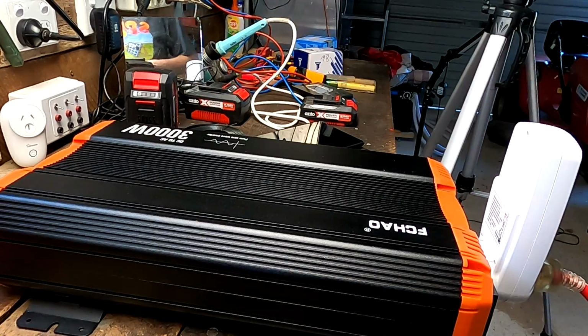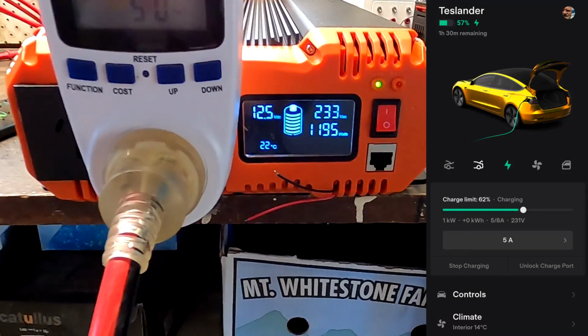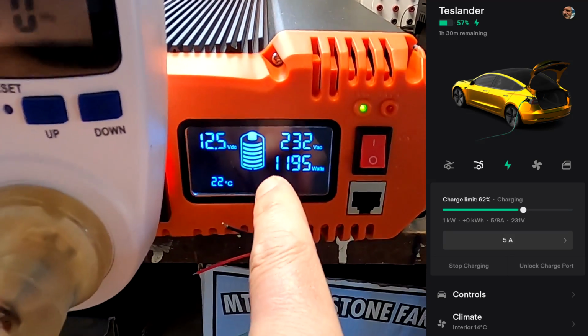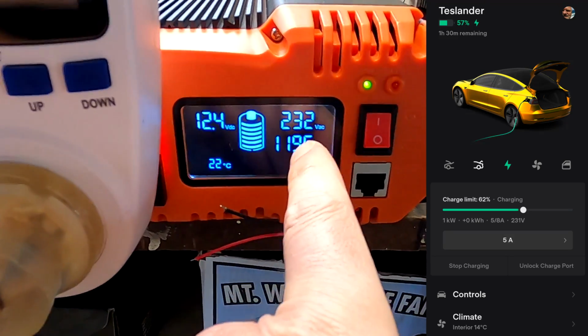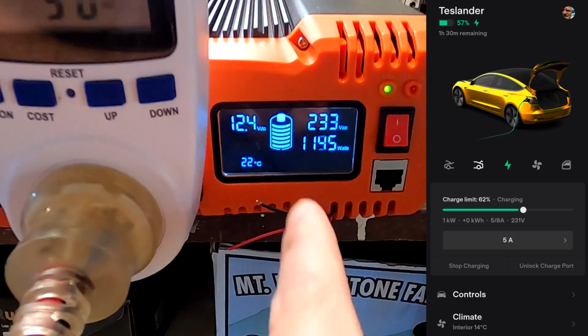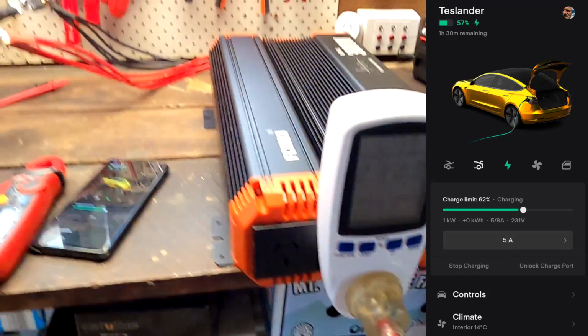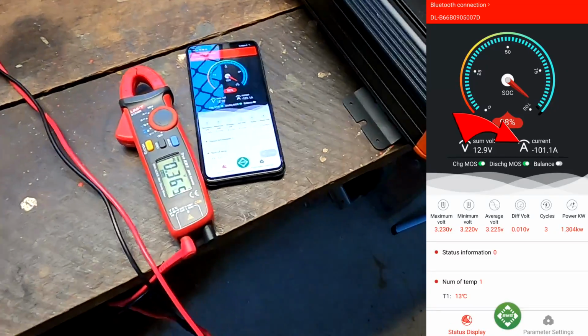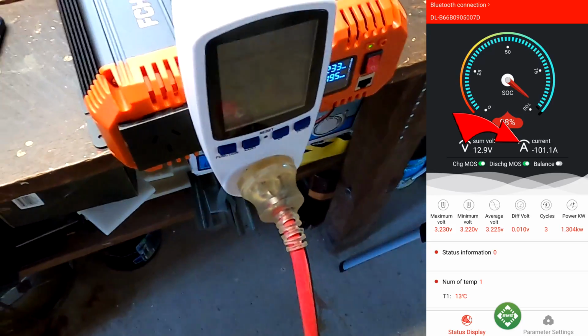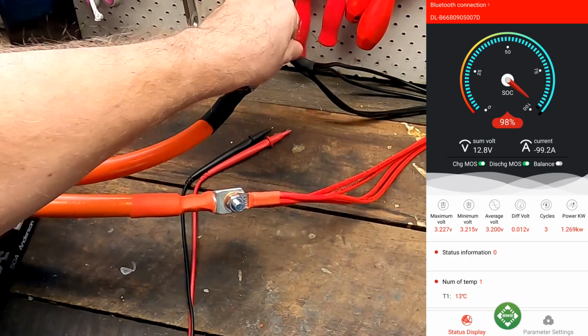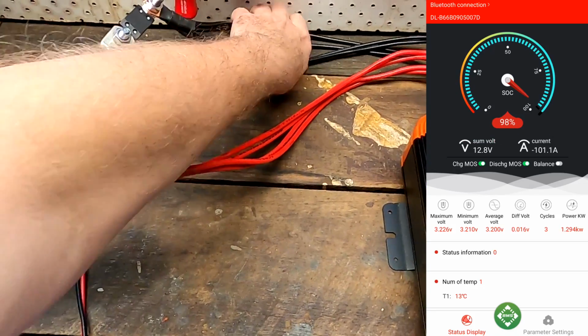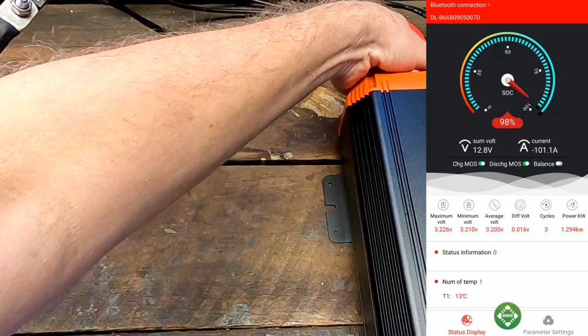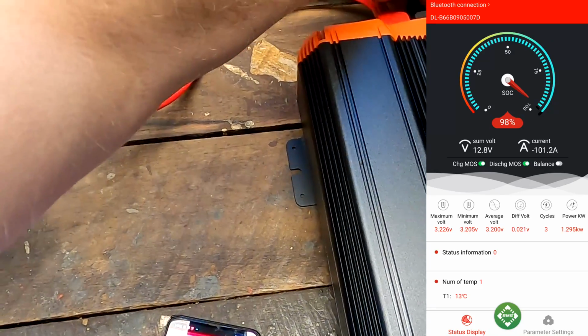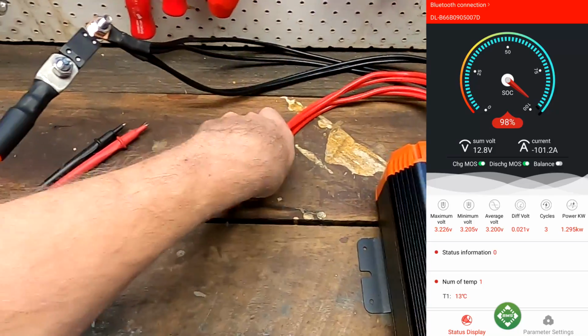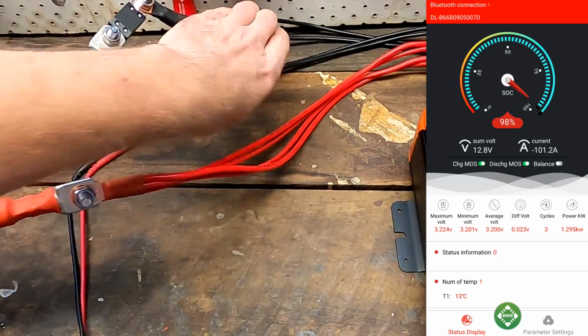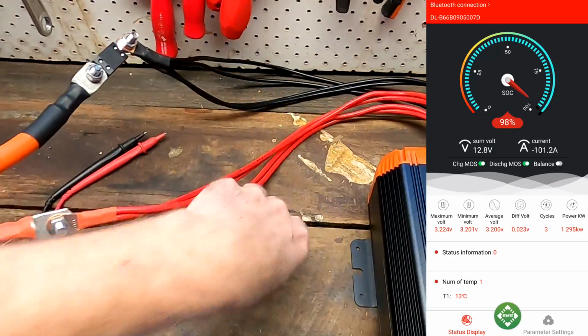Okay, so we are now charging - 1100, 1200 watts. We are pulling 230 volts. Everything seems to work just fine. In the app you can also see we are pulling around 100 amps now from the battery. I'm checking these cable connections as well as the cables, just to ensure there's nothing getting warm, because this is all equipment supplied by the inverter manufacturer, so it's not my own.